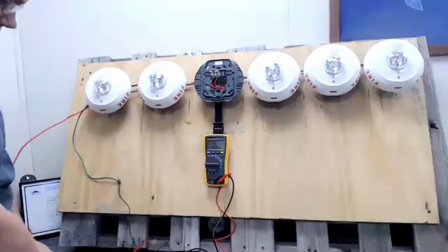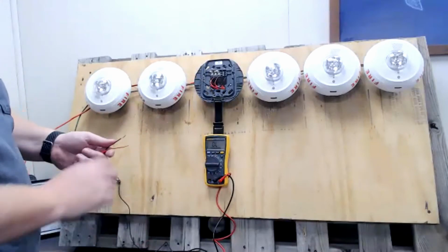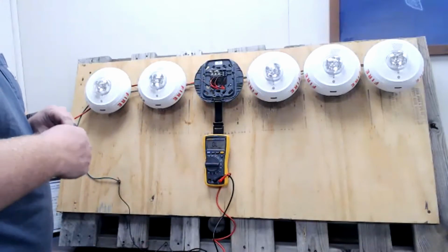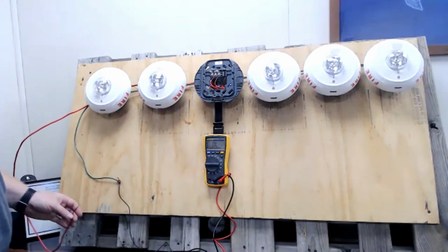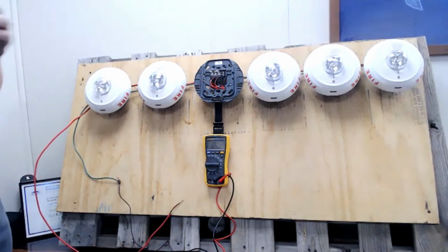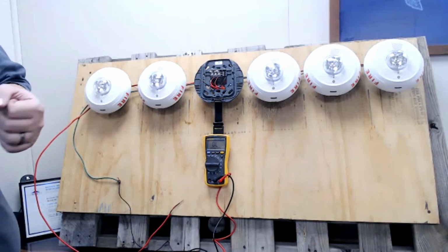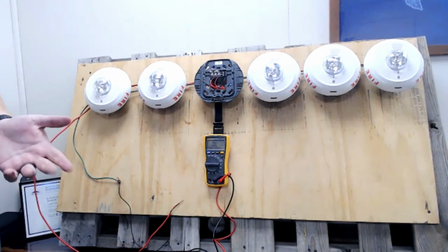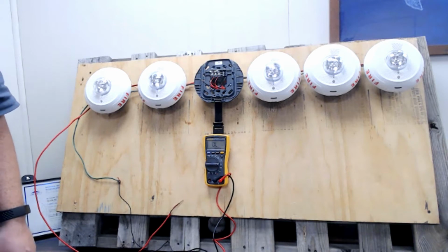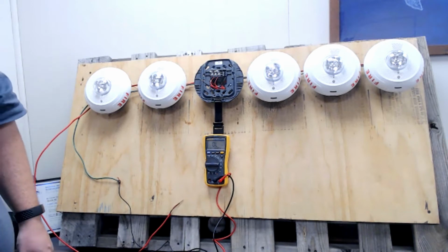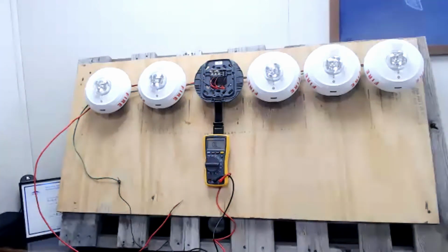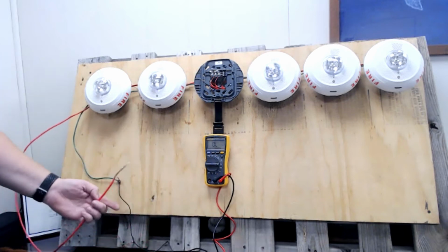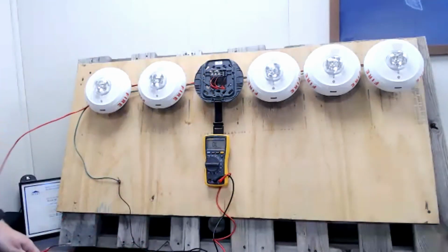So now also similarly, you're going to want to do something to help you identify your home run. So I'm going to short it again. One of the other things I like to do, if I don't short it, is get a different valued resistor. So this is a 4.7 k ohm circuit. I might have a 15 k ohm resistor on me. I typically keep some 33 k ohms in my bag because they're different than pretty much everything, no matter what system I'm working on. Having a 33 k ohm is really handy for that. And so I can put that 33 k ohm on here, and I know that if I see 33 k ohms, that is my home run, and it's not some other short that's in the field.